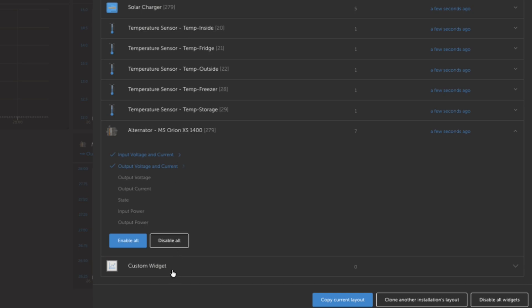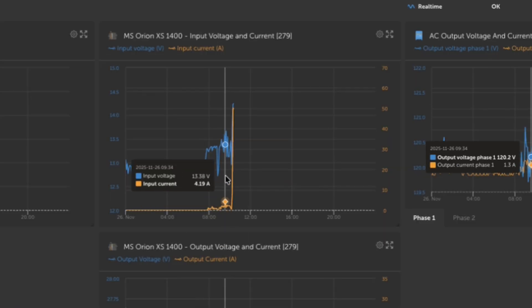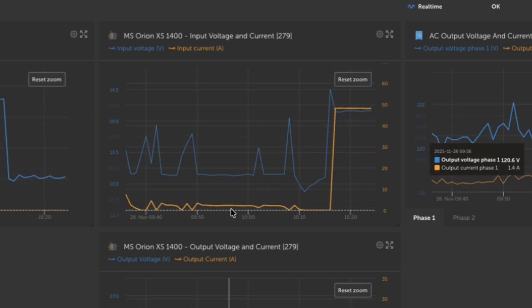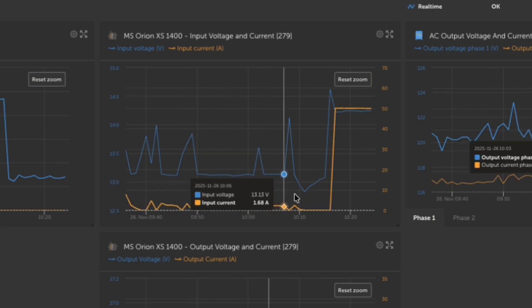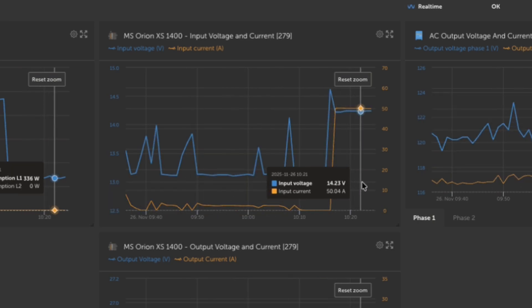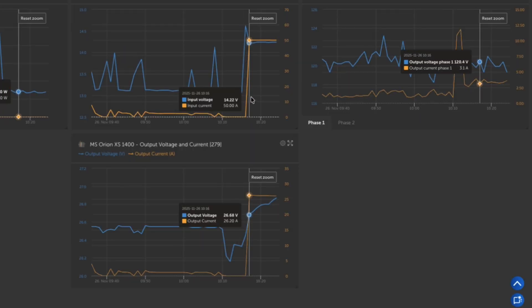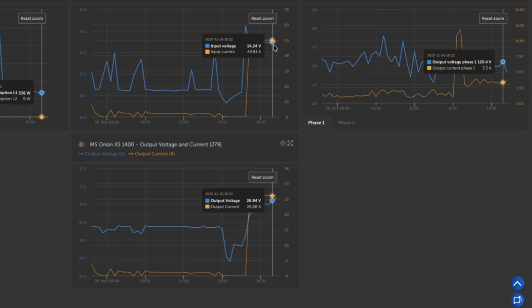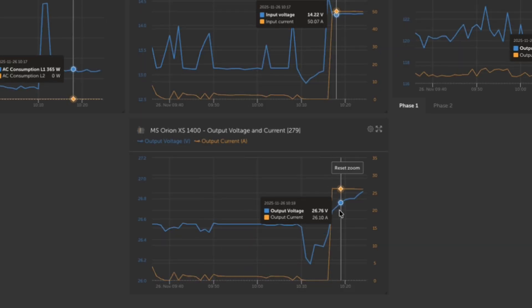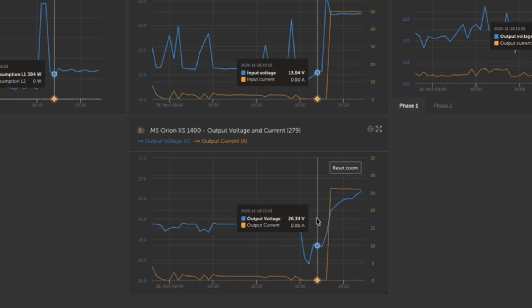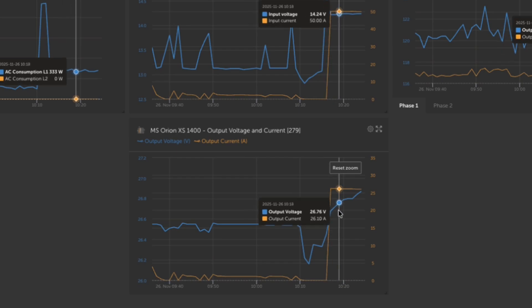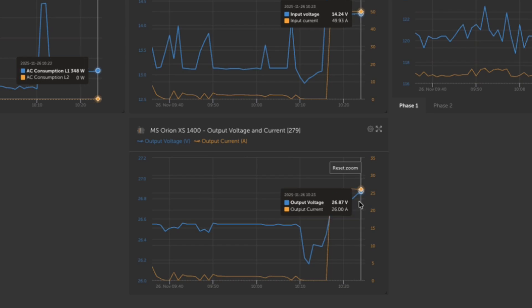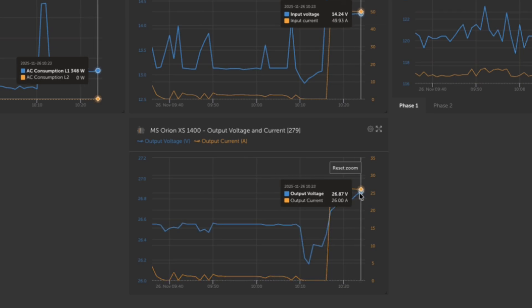Really handy to be able to get all this. You also can do custom widgets and pull up any of this data and compare it to something else in your system. So super useful. Also incredibly handy for being able to troubleshoot and monitor and just purely see how effective this has been. So I'm going to zoom right in on the last few minutes. So it was off. We had our input current pretty much settled at zero, but now it's on. Look at that. 50 amps of input current and the input voltage spiked. That was what triggered our system to turn on. And now it is happily charging away. And now our output voltage. You can see the front edge of the curve happening here. So the storage bank, our lithium bank was down at 26 volts. And then as this charger kicked in, it's already starting to bring this voltage up and it will bring that up until it finishes the bulk cycle. And then it will begin to do the absorption cycle where this amperage will drop and the voltage will be maintained at a flat rate.